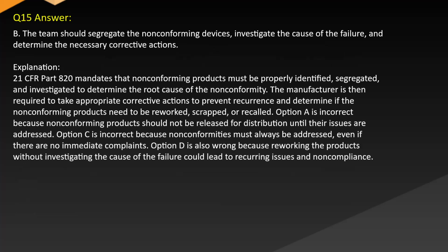Answer: B. The team should segregate the non-conforming devices, investigate the cause of the failure, and determine the necessary corrective actions. Explanation: 21 CFR Part 820 mandates that non-conforming products must be properly identified, segregated, and investigated to determine the root cause of the non-conformity.